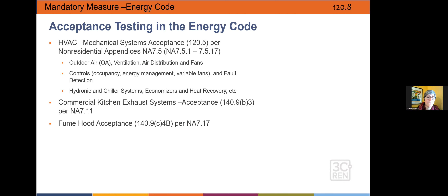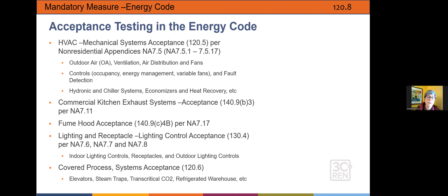The Energy Code specifically requires acceptance testing for non-residential systems: outside air distribution, fans, controllers, fault detection, and basically anything mechanical that uses energy. It also includes commercial exhaust and fume hood systems, lighting and receptacle controls, outdoor lighting controls, and covered processes like elevators, moving walkways, steam traps in boiler systems, transcritical CO2 refrigerant systems, and refrigerated warehouses.